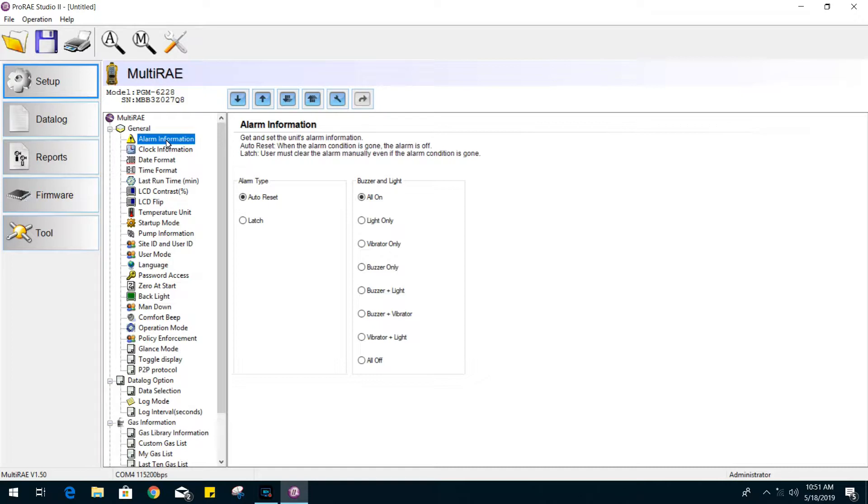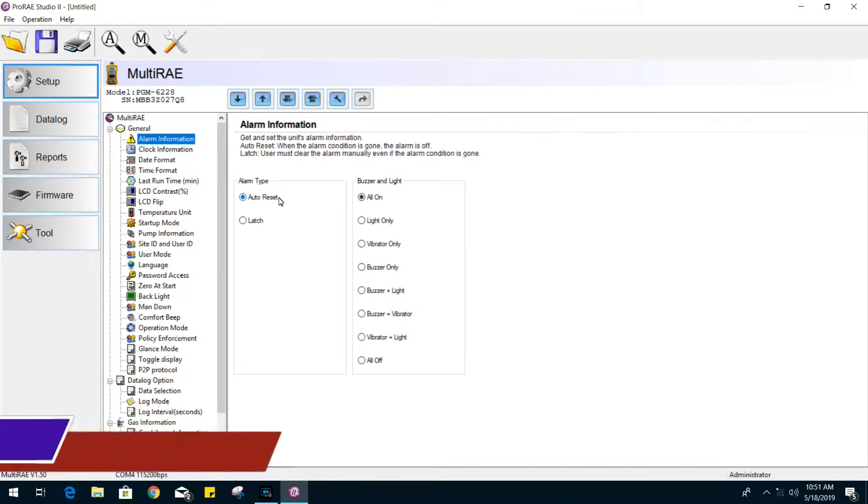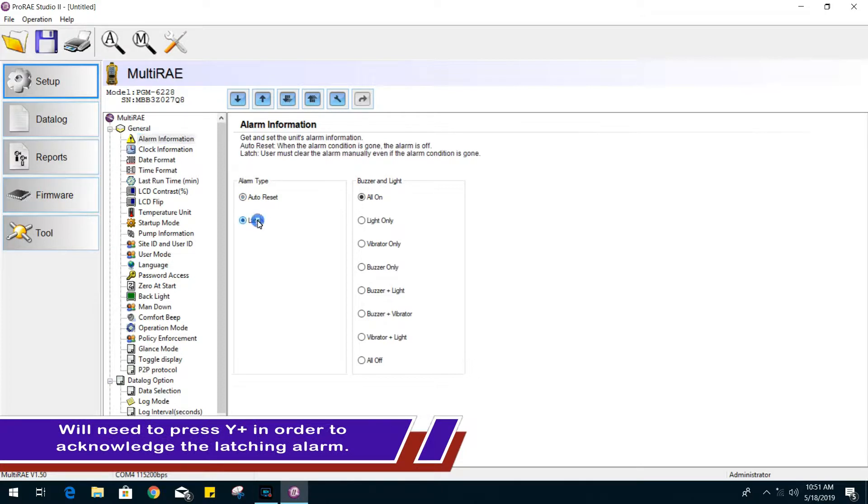If you go to alarm information, we have alarm type settings, auto reset or latch. If your unit goes into alarm and then stabilizes to a normal reading, the alarm should restore itself when auto reset is enabled. When latch is selected, the alarm will continue to sound until it's acknowledged by a button press.